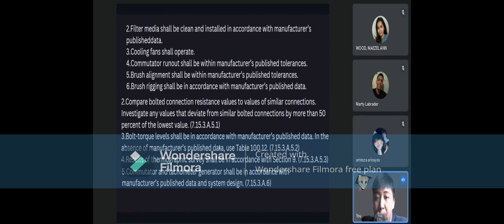5. Brush alignment shall be within manufacturer's published tolerances. 6. Brush rigging shall be in accordance with manufacturer's published data. 2. Compare bolted connection resistance to values of similar connections. Investigate any values that deviate from similar bolted connections by more than 50% of the lowest value, in accordance with 7.15.3.A.5.1. Bolt torque level shall be in accordance with manufacturer's published data. In the absence of manufacturer's published data, use table 100.12 in accordance with 7.15.3.A.5.2. 4. Results of thermographic survey shall be in accordance with section 9, in accordance with 7.15.3.A.5.3.